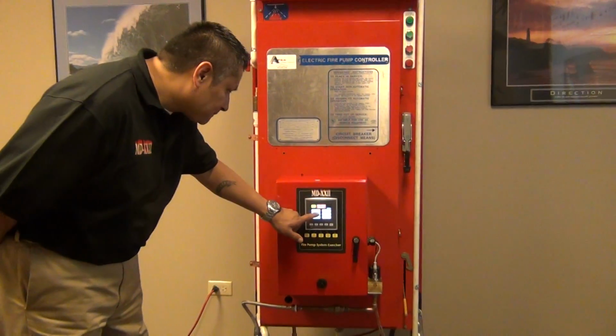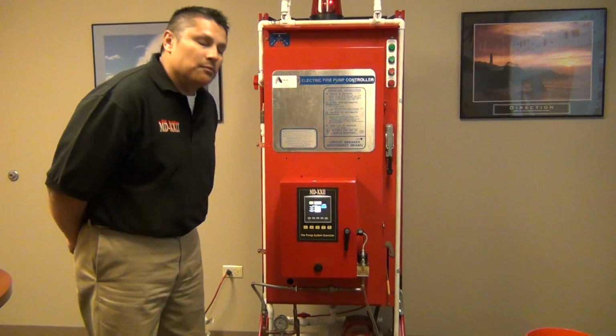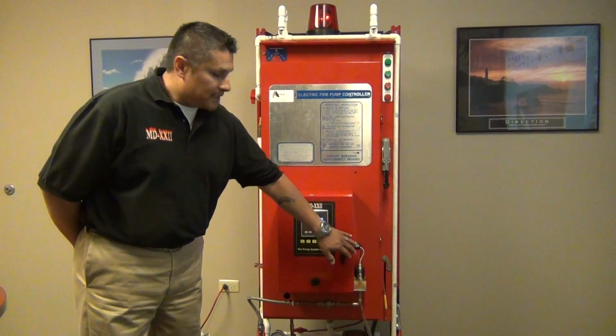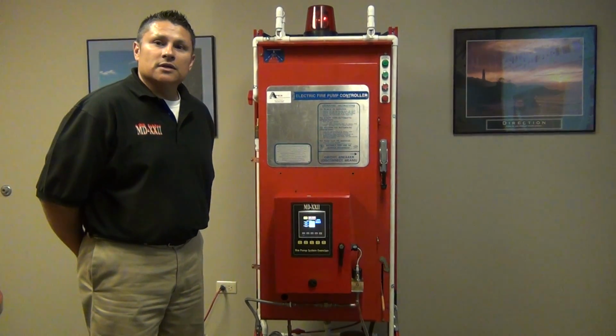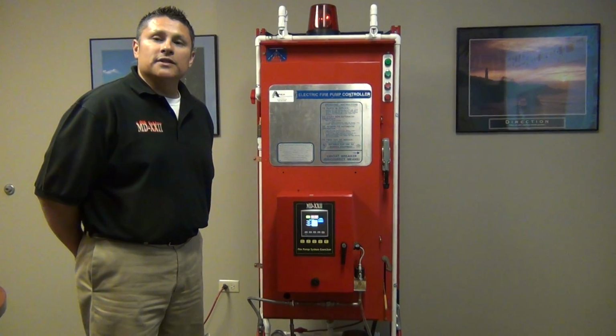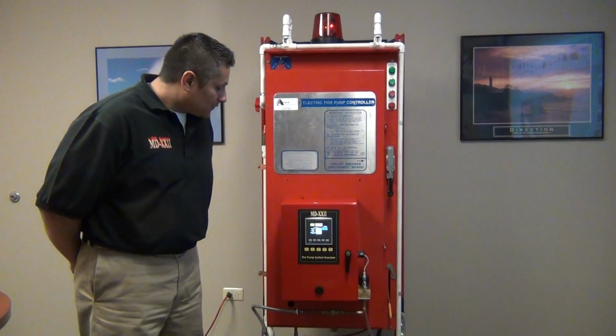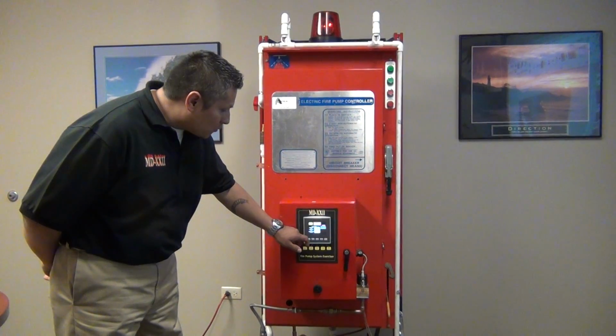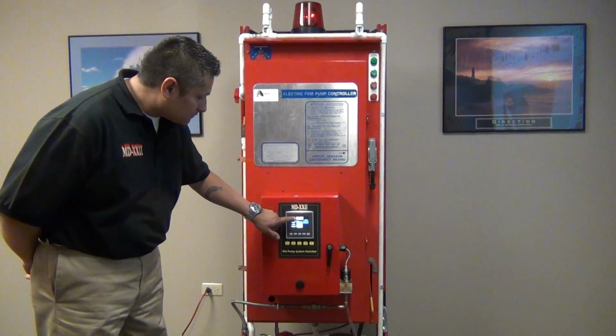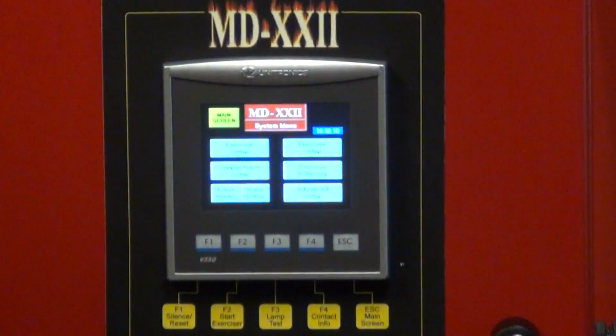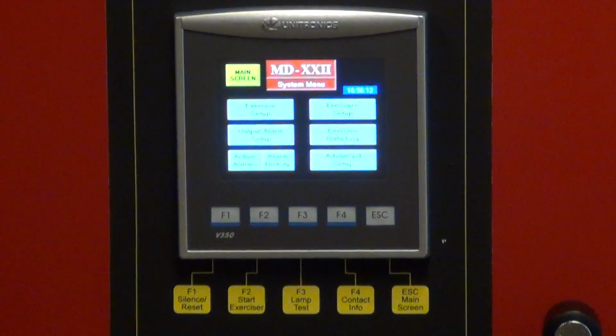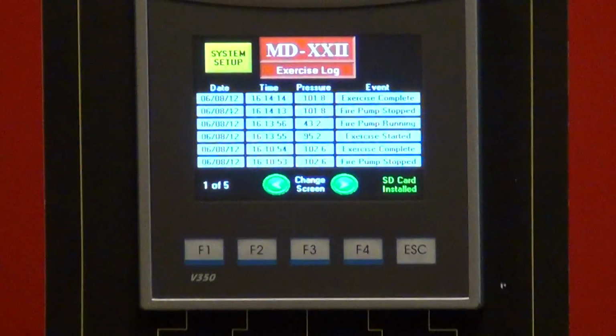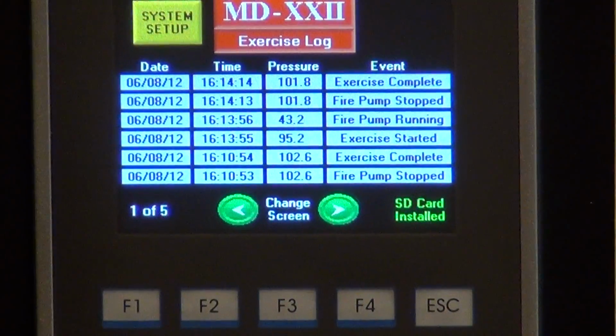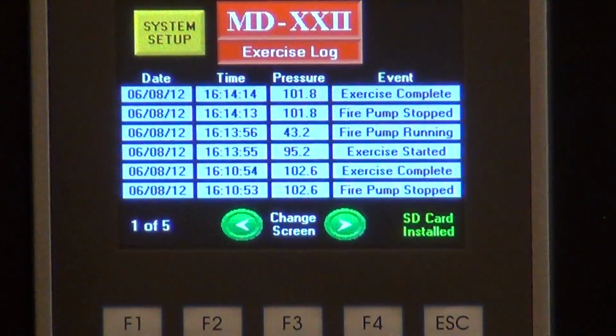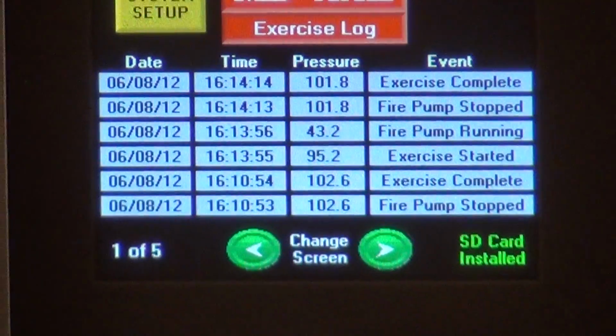At the same time, the MD22 offers you the ability to set an integral pressure transducer to start your fire pump controller in the event your fire pump controller does not start through its pressure switch. You can also set your high and low pressure alarms right here on the screen. The MD22 will also allow you to set your exercise and be able to visually see the exercises on the event and data log.